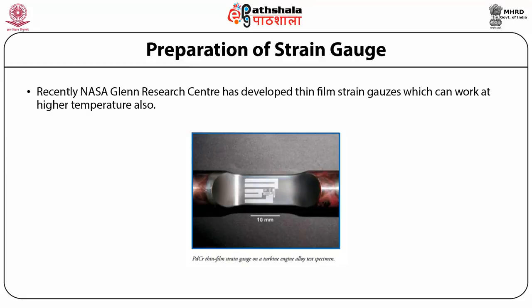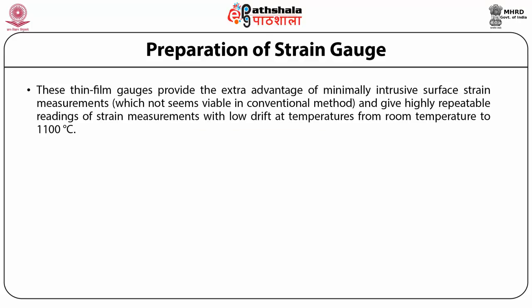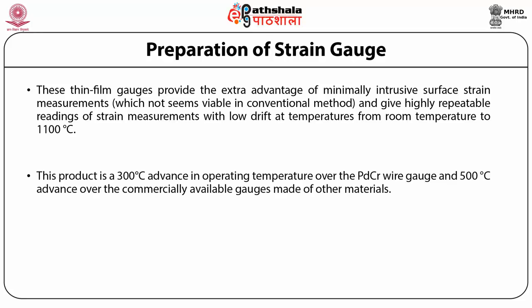Recently, NASA Glenn Research Center has developed thin film strain gauges which can work at higher temperatures. The picture of their final product shows a palladium-chromium thin film strain gauge on a turbine engine alloy test specimen. These thin film gauges provide the advantage of minimally intrusive surface strain measurements, giving highly repeatable readings with low drift at temperatures from room temperature to 1100°C. This product represents a 300°C advance in operating temperature over palladium-chromium wire gauges and a 500°C advance over commercially available gauges made of other materials.